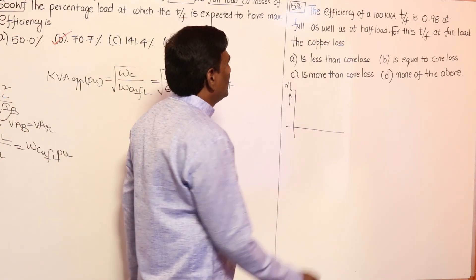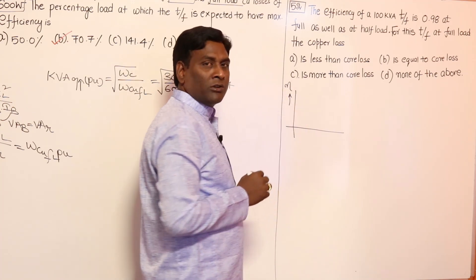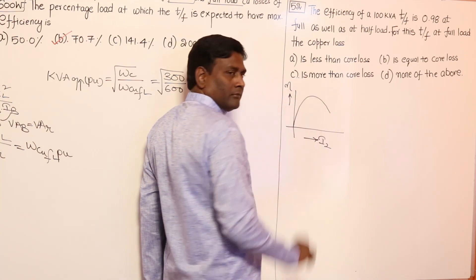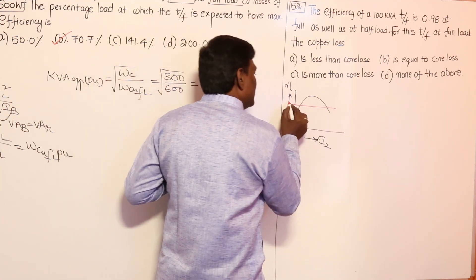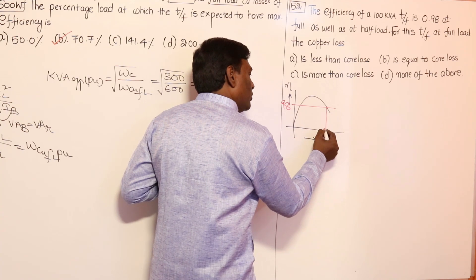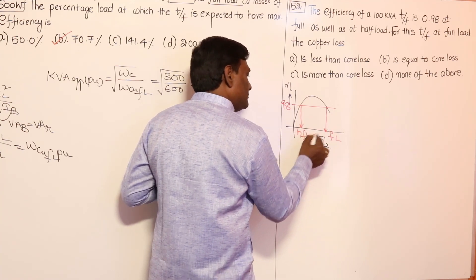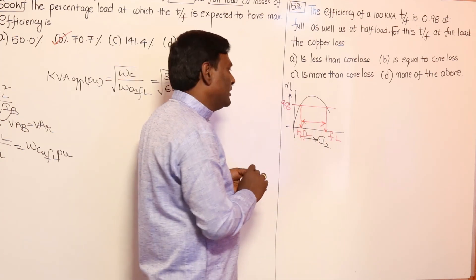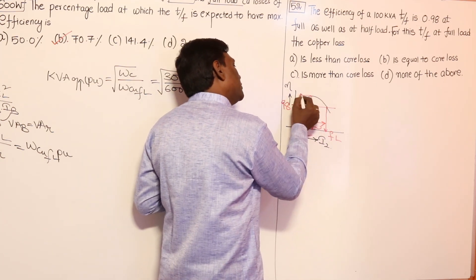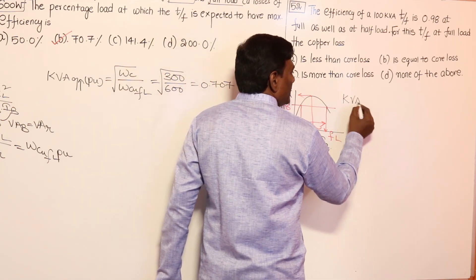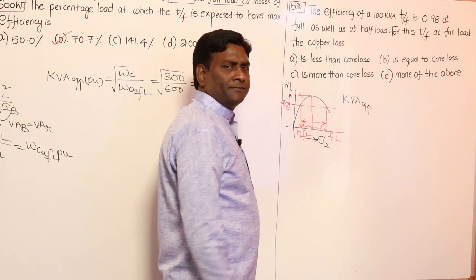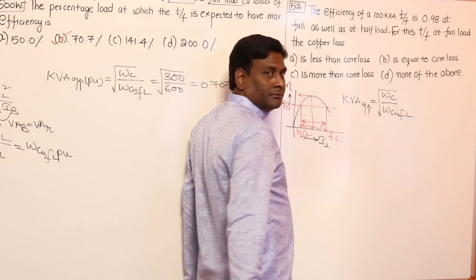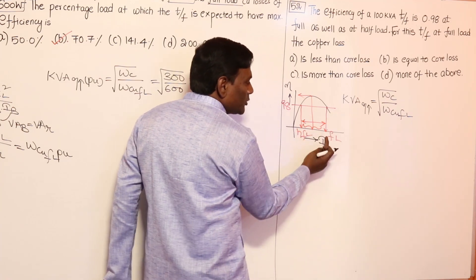Since power factor is not mentioned, it should be considered constant. The efficiency is 98 percent at full load and also at half full load. Maximum efficiency should occur between half full load and full load. The KVA at maximum efficiency in per unit equals the square root of core loss divided by full load copper loss.